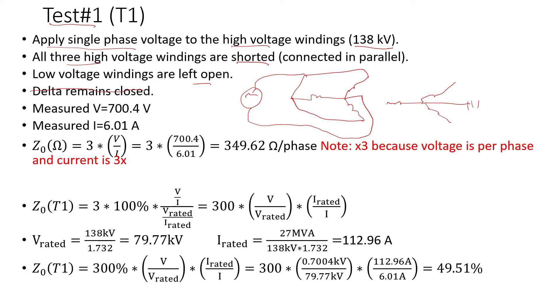Since there is no delta, we don't need that. In this case, the measured voltage is 700.4 volts and the current is 6.01 amps. The equation to calculate the zero sequence impedance in ohms is three times the measured voltage divided by the measured current: 3 × 700.4 / 6.01 = 349.62 ohms per phase.